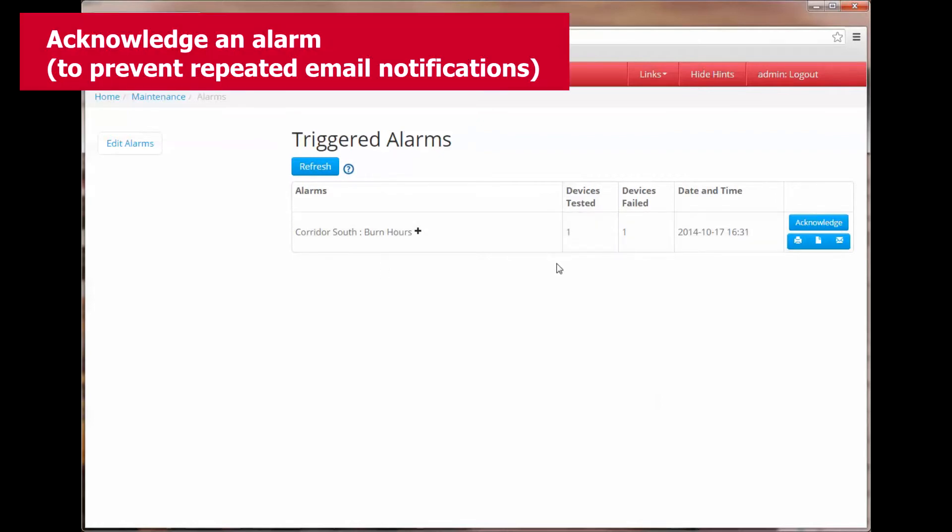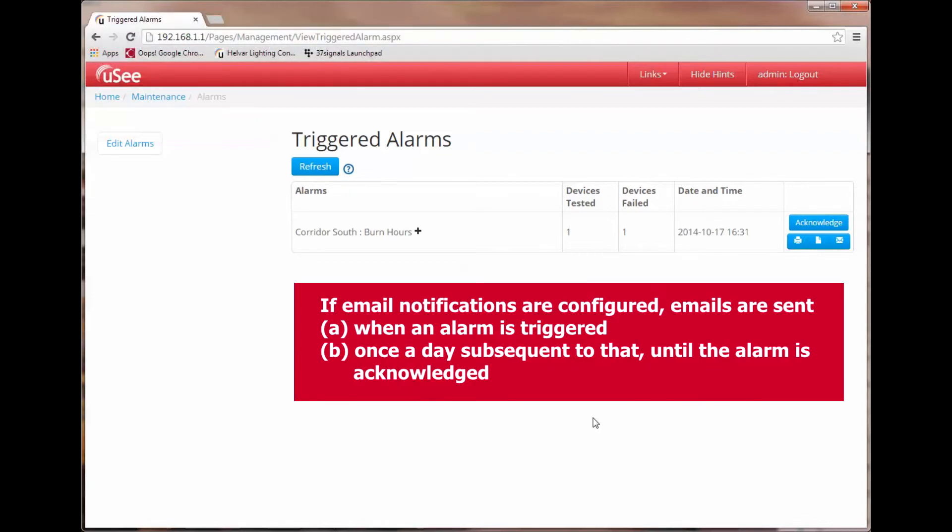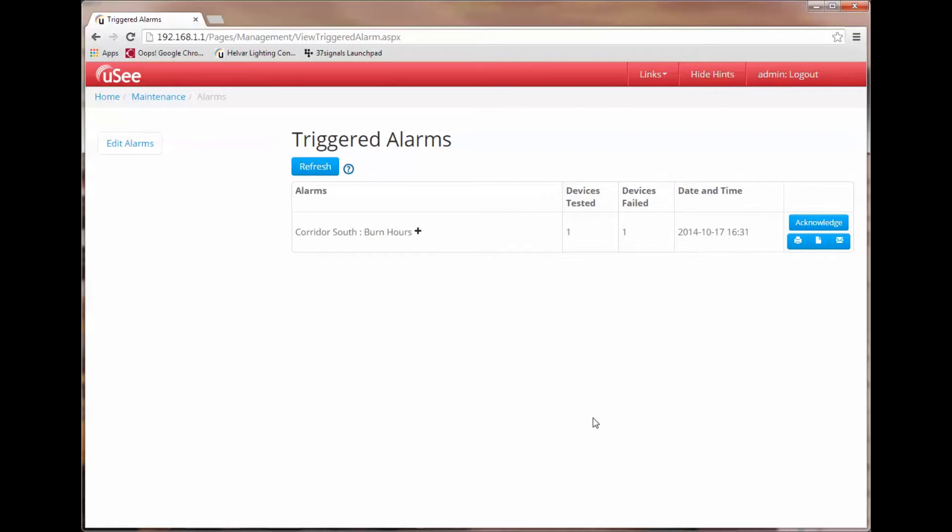Okay so from here I can now acknowledge that alarm. What does acknowledgement mean in this instance? We already know that when an alarm is triggered it can cause an action. It will continue to cause that action periodically until it has been acknowledged. So for instance if we are sending an email because the burn hours have exceeded our threshold, the email will be repeatedly sent until the alarm has been acknowledged.